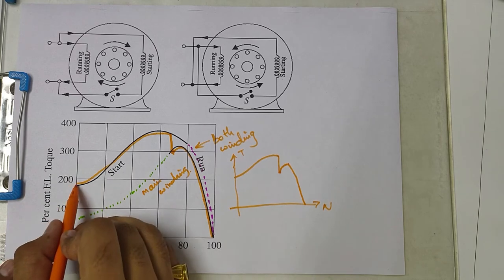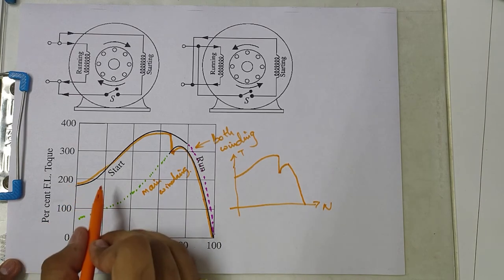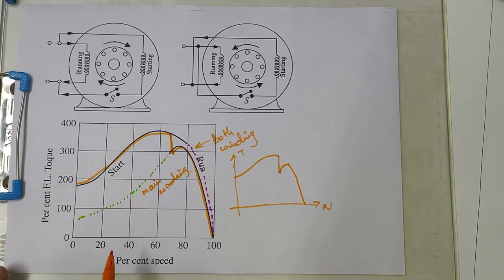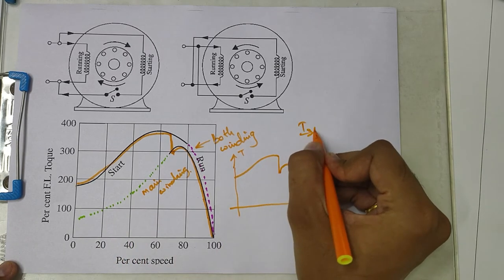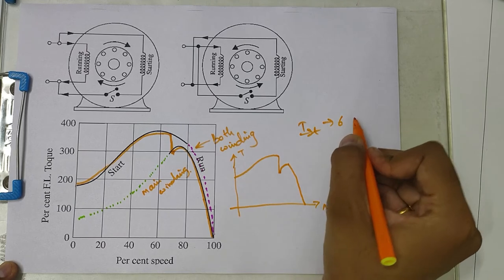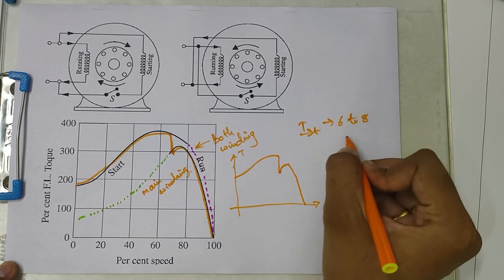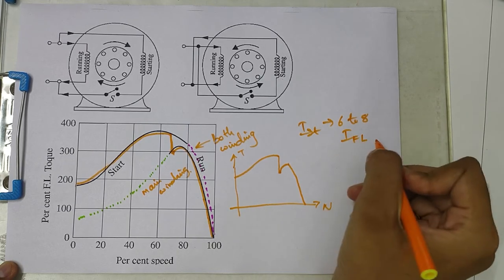The starting torque, as you can see here, is 150 to 200 percentage of full load torque, with a starting current of 6 to 8 times the full load current. The starting current is 6 to 8 times the full load current.